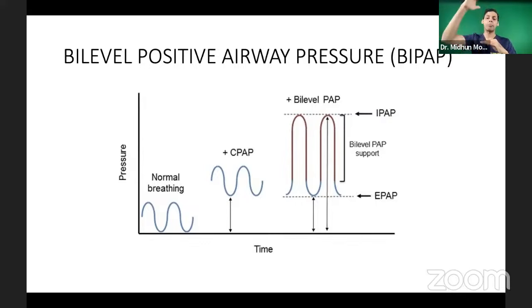And the difference between IPAP and EPAP creates a pressure gradient: a higher pressure during inspiration and a lower pressure during expiration. Of course, you know the principle. Whenever there is a pressure gradient, air will flow from higher pressure to lower pressure, so this patient will get an extra volume of air. The BiPAP machine gives this pressure by the flow of air. If you connect this mask to yourself, you can see there will be a huge, continuous flow of air, and this pressure is generated by this continuous flow.